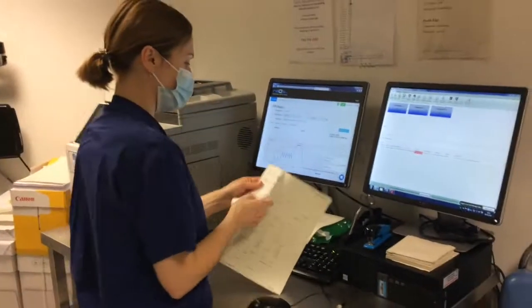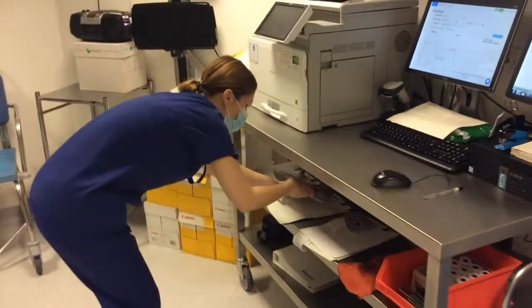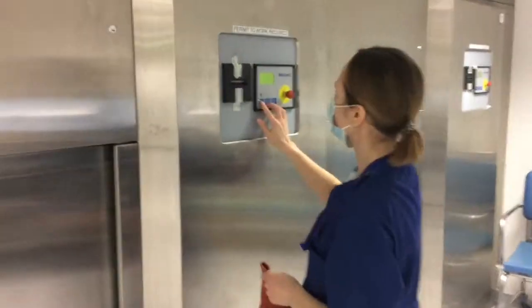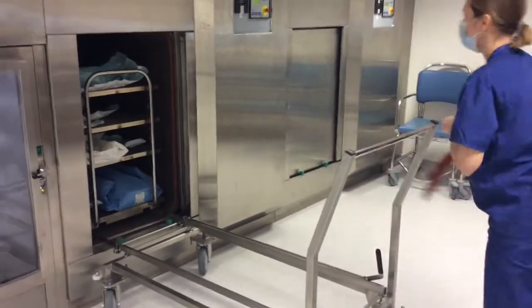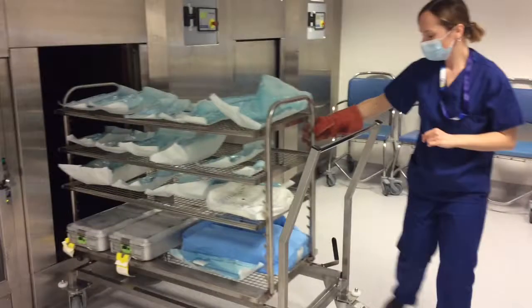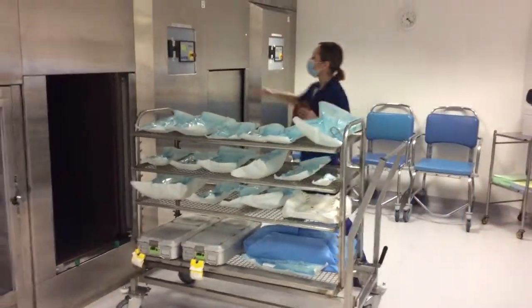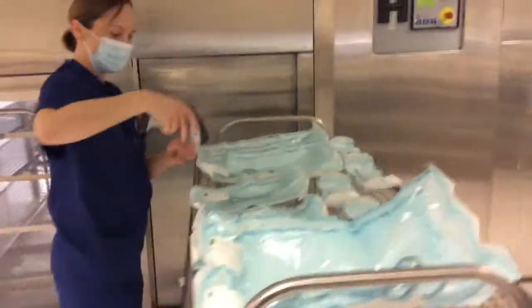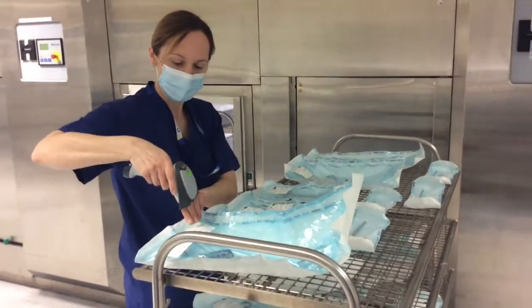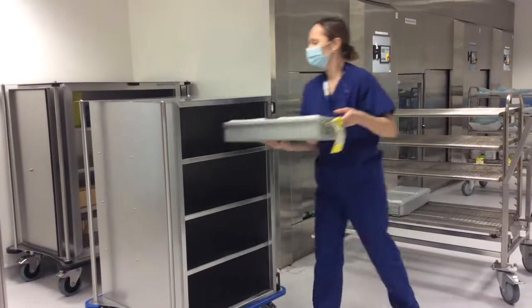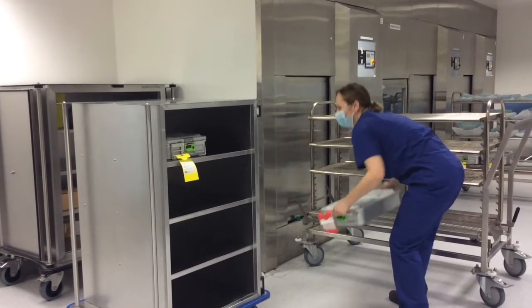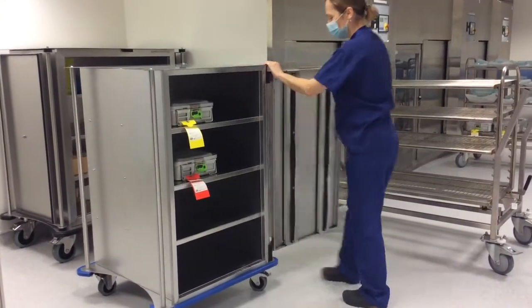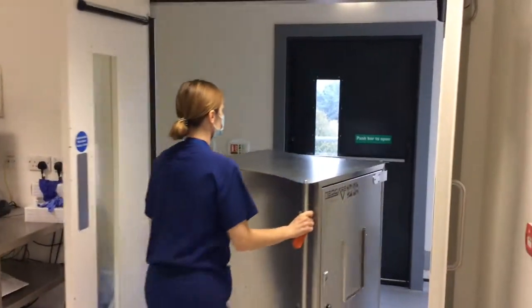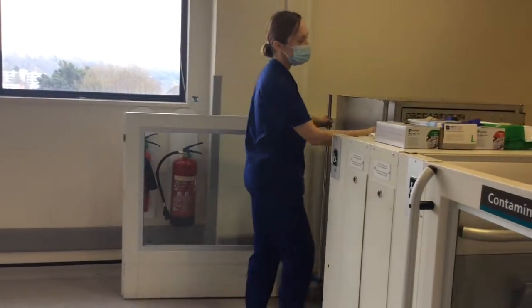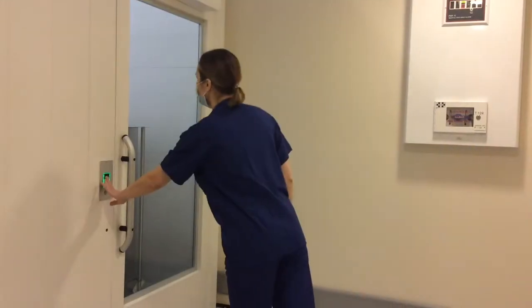The kit then comes out of the autoclave and is scanned, so it can be recorded that the equipment has been processed. The trays are then left to cool for a minimum of 1 hour before being loaded up and taken to the correct departments. The tamper-proof seals and external labels have heat-sensitive indicators. Once in the autoclave, providing the specified temperature is reached, the indicators change colour. When the cycle is finished, these act as a visual indicator to show that the autoclave has reached the correct temperature. The whole sterilisation process takes a minimum of 4 hours depending on the urgency of the equipment required.